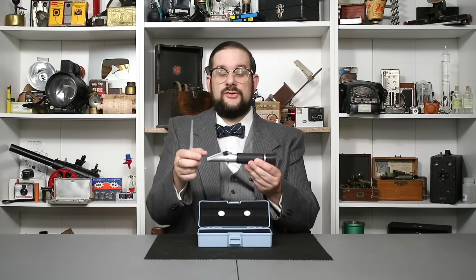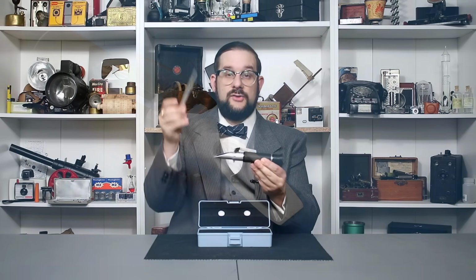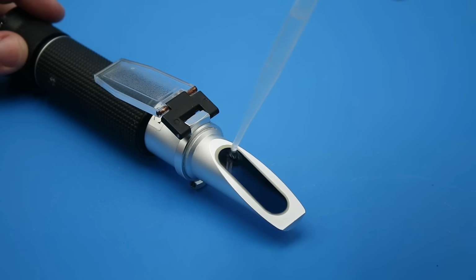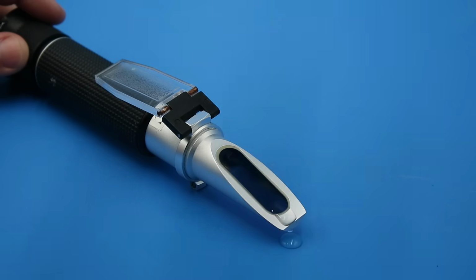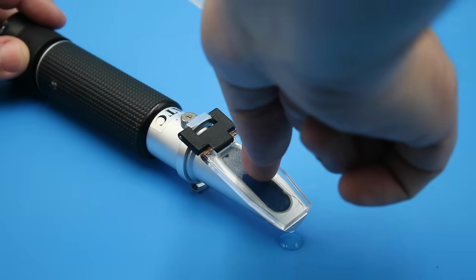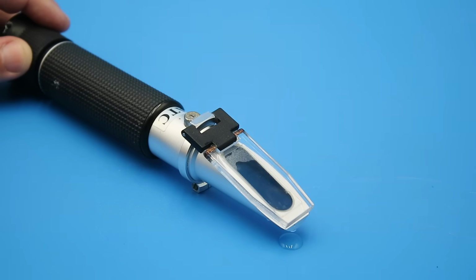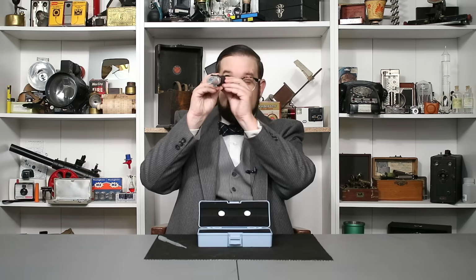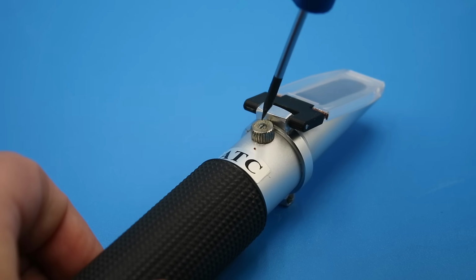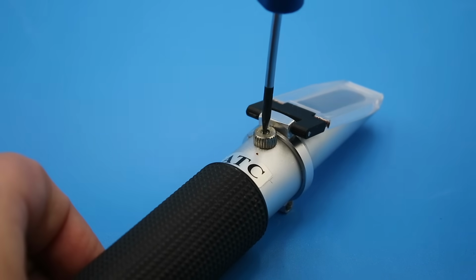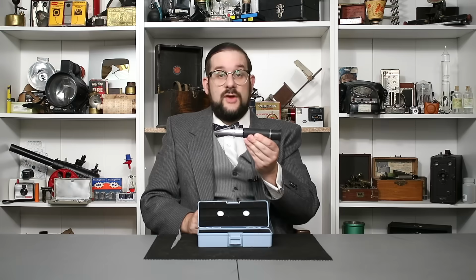So to use this, you first have to calibrate it, and you do this by using an eyedropper, put a few drops of distilled water on the surface of the prism. You then close the illuminating cover, which spreads the liquid into a thin, even film. You then hold this up to a bright light and check to see if the shadow boundary falls on zero. If it doesn't, you take a small flathead screwdriver and turn the adjustment screw until it does. You are now ready to take your reading.